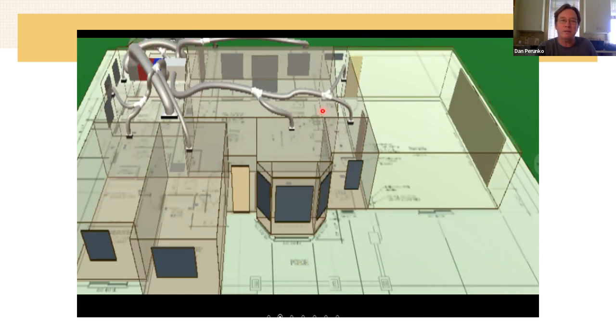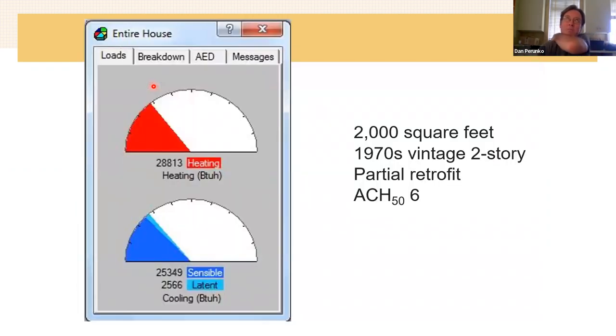Like if you built a duct system that looked like what's in that picture, it'd be a really bad duct system. Too big and wavy. What we're looking for is compact and very straight lines. And like I said, duct system building is a class we could spend days on. So these are sort of typical load calcs. Our industry tends to oversize things. So the importance of this is that this number is the size of the house, and this is a lot less capacity than would typically get installed, and oversizing causes significant losses, right?